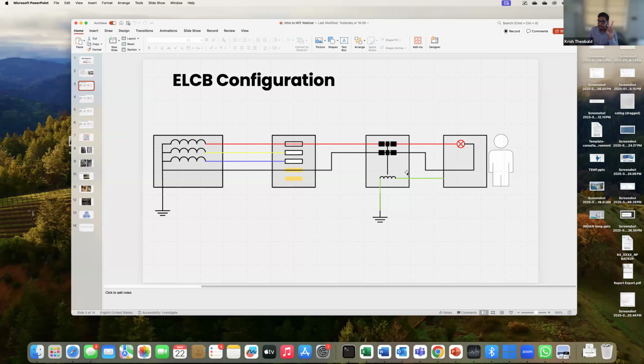Now, there are 2 types of settings when you perform a test: a low current test and a high current test. I'm just seeing if I have an instrument here to show you. No, I don't. The low current test will ensure that the device doesn't trip. The high current test will cause tripping of the device. Whether it is different for ELCB versus RCCB, I cannot say. Maybe an ELCB has a lower threshold for tripping. But in any case, you should not be using an ELCB. It should be replaced by an RCD, because the standard requires a device conforming to IS 12640 or 62423. There is no option for an ELCB to be used.